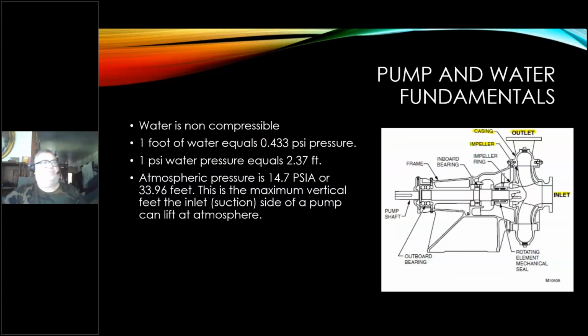For those of you who may not know what the parts of a pump are, let's talk a little bit about pumps and fundamentals. So we talk about pumps as inlet and outlet, of course. Typically we talk about water. Water is probably the most common thing that we pump. A foot, when we talk about the pressures, a foot of water equals 0.433 psi. So when we talk about pump curves, it's going to measure the head in feet of water. That's pressure.